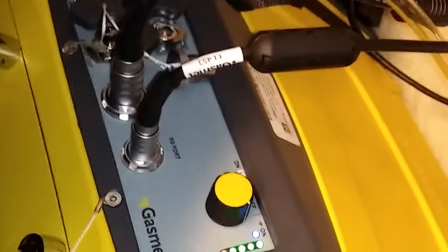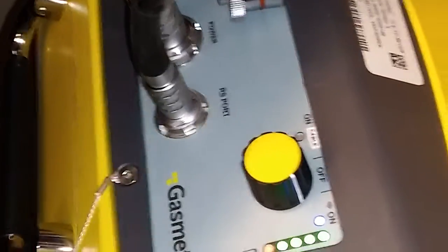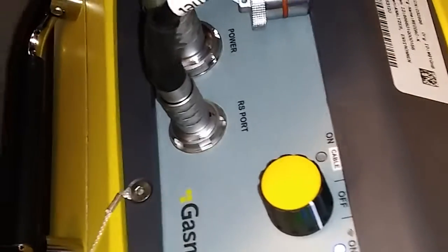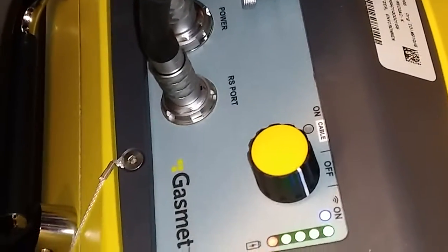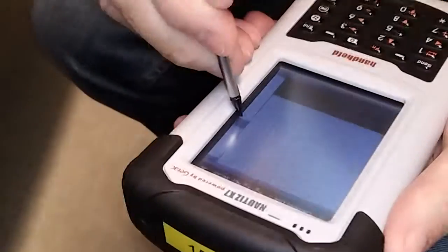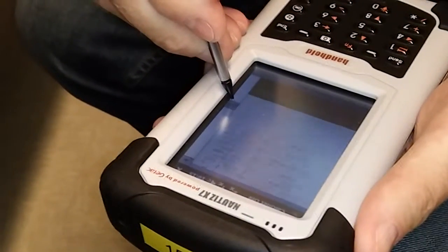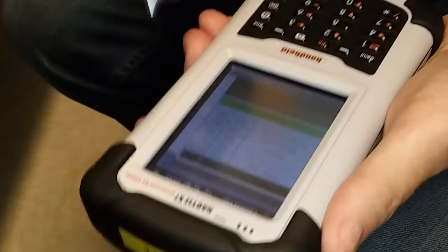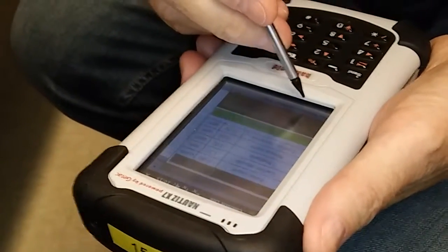This thing now showed 127, and methane and nitrous is 0. So according to that cal, we're okay. But I'm surprised that I don't hear the fan going when it does a calibration. Okay, let's take that off there one more time and just take a measurement, and we'll see what our...